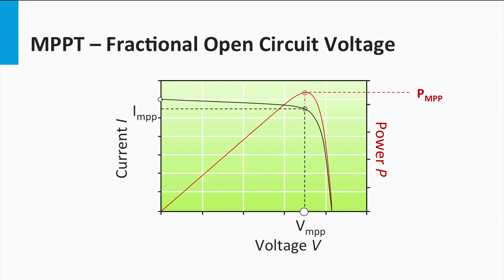One of the most common MPPT techniques in the indirect tracking category is the fractional open-circuit voltage method. This method exploits the fact that a good approximation of V_MPP is given by a constant K multiplied by the open-circuit voltage. This constant K for crystalline silicon is usually found to be around 0.7 to 0.8 in practice. In general, constant K is based on the PV technology and the kind of solar cells in use.